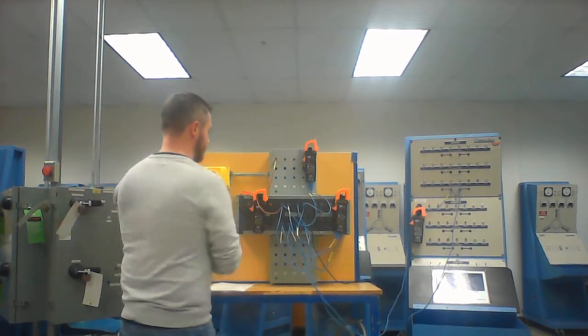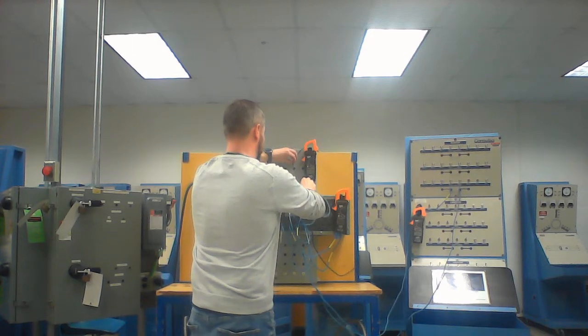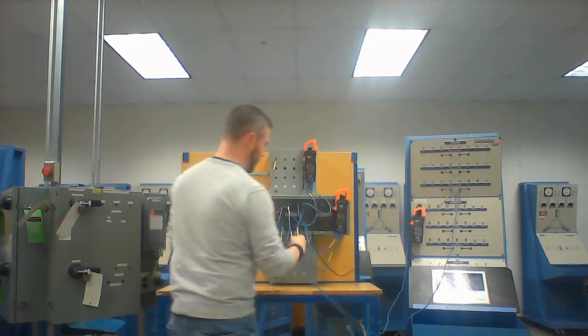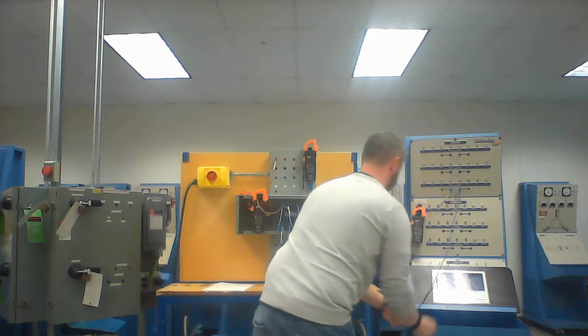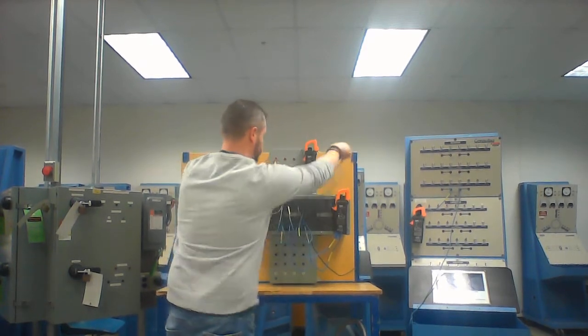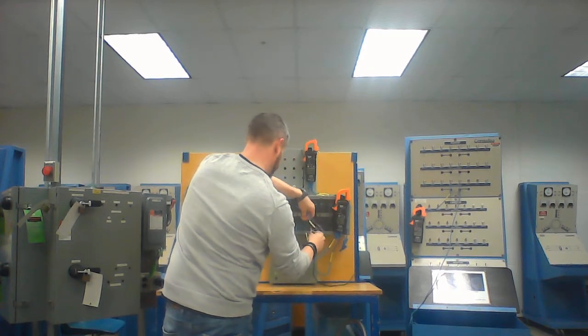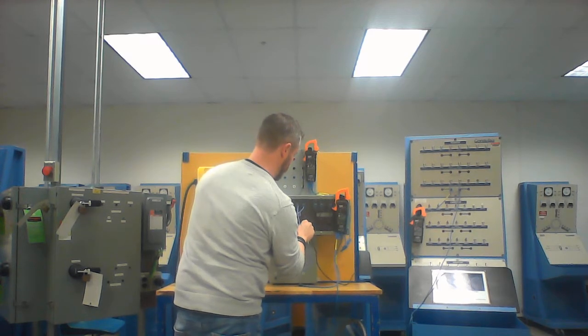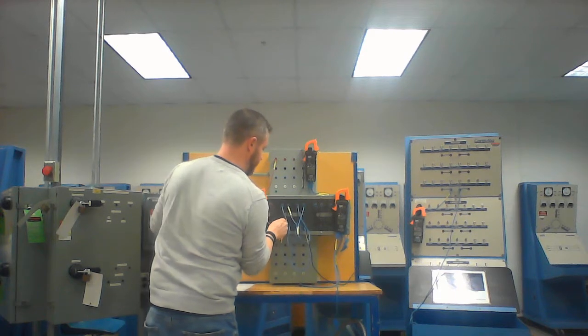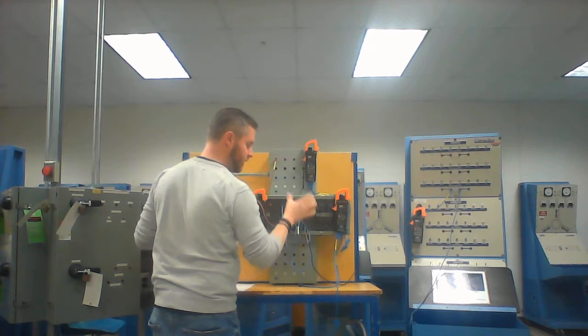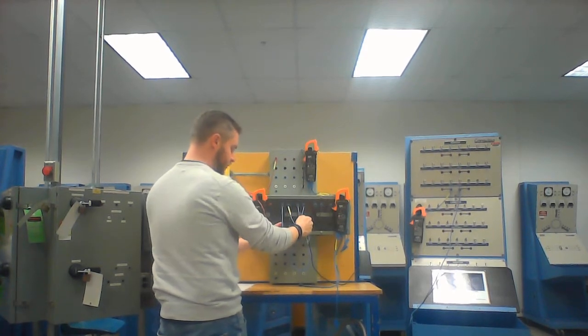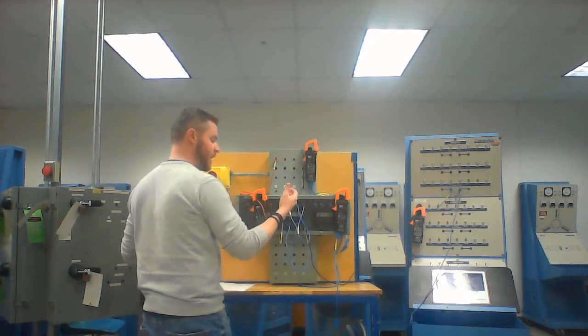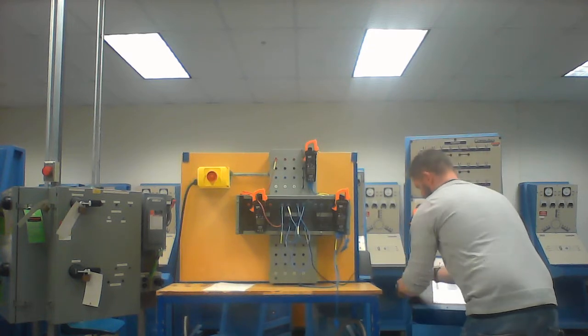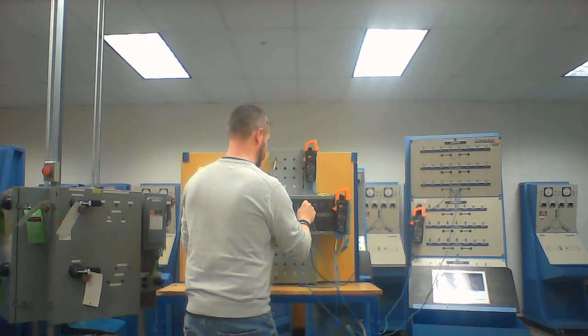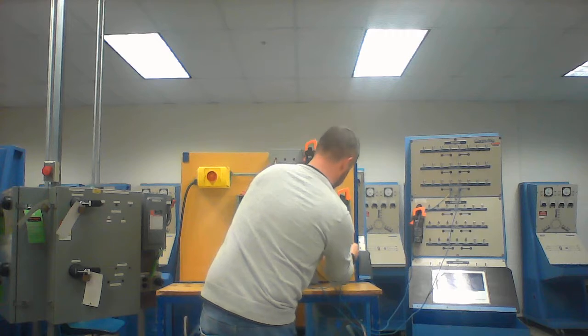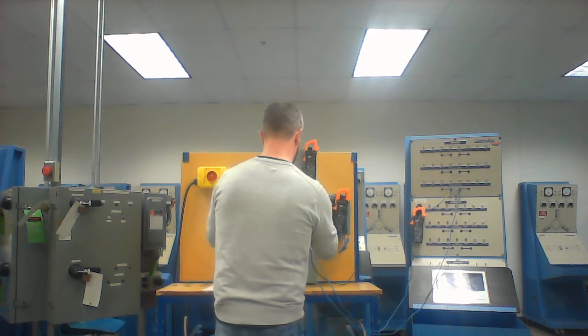Step number 12, we're going to rearrange our transformer a little bit. Very similar to last week, I'm going to use the X side of my transformer as my primary, and the H side of my transformer as my secondary. So I'm going to change my meters around just a little bit and change my connections. I also have to observe that I'm doing 120 volts on the X side of the transformer, not 208 like we did last week, generating 330 volts out of the H side, doing a parallel configuration that we did last week. So now I'm going to put 120 volts down to my X side, and I'm going to expect to see a certain voltage out of my H side, which is now going to be my new secondary. These guys are all in the same position. This is secondary voltage.